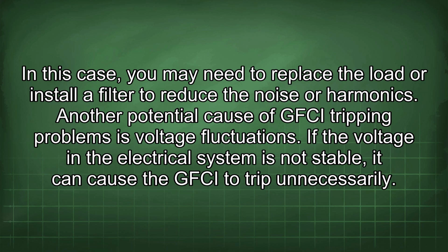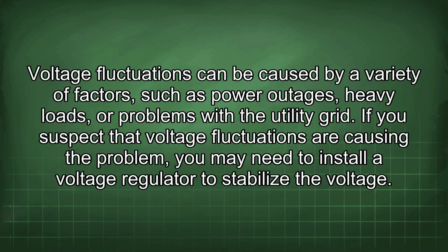Another potential cause of GFCI tripping problems is voltage fluctuations. If the voltage in the electrical system is not stable, it can cause the GFCI to trip unnecessarily. Voltage fluctuations can be caused by a variety of factors, such as power outages, heavy loads, or problems with the utility grid.